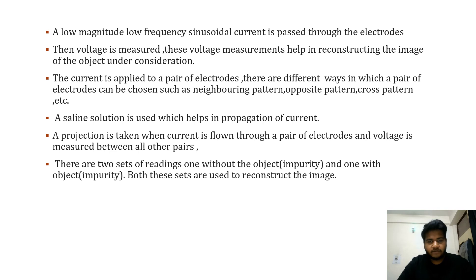Now let us look at the process of electrical impedance tomography. A low magnitude, low frequency sinusoidal current is passed through the electrodes, then voltage is measured. These voltage measurements help in reconstructing the image of the object under consideration. The current is applied to a pair of electrodes chosen using different patterns such as neighboring, opposite, or cross pattern. A saline solution is used which helps in the propagation of current easily.